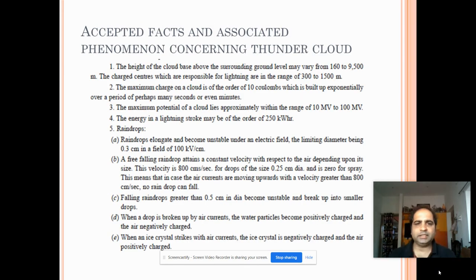So next point is lightning. Some of the accepted facts and associated phenomenon considering thundering clouds are: the height of the cloud should be between 160 to 9500 meters. The charge centers which are responsible for lightning are in the range of 300 to 1500 meters. The maximum charge on a cloud is of the order of 10 coulombs and exponentially increases over a period of perhaps many seconds or minutes. The maximum potential of a cloud lies approximately within the range of 10 megavolts to 100 megavolts. The energy in the lightning stroke may be of the order of 250 kilowatt hour.